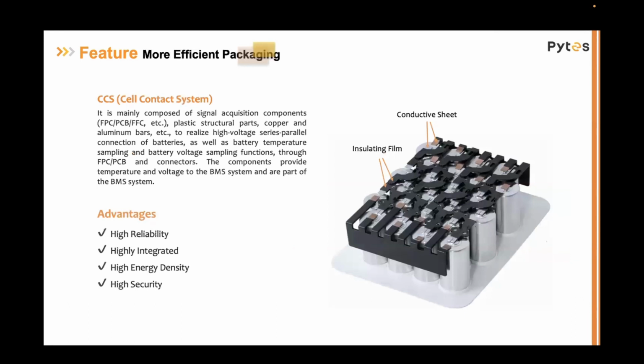This is an in-depth look at how our cells communicate with the BMS unit. We use flexible printed circuit boards so each cell communicates directly with the BMS, not just its charge level for balancing, but also the ambient temperature we were talking about, so we can turn on the heating pad if needed. This setup is very high resolution, very high security, and the connections make communications from the cells to the BMS a lot more efficient.